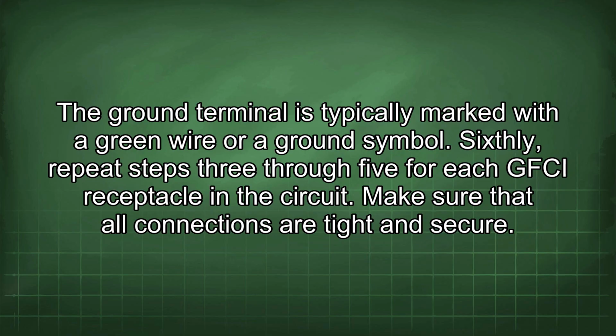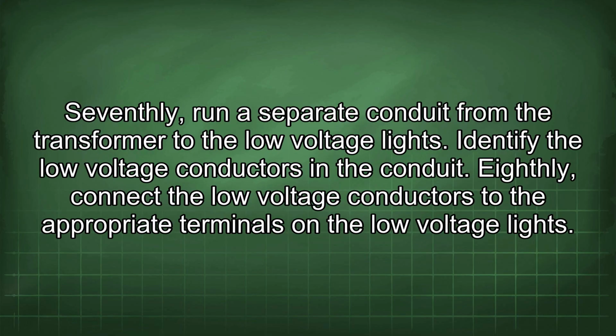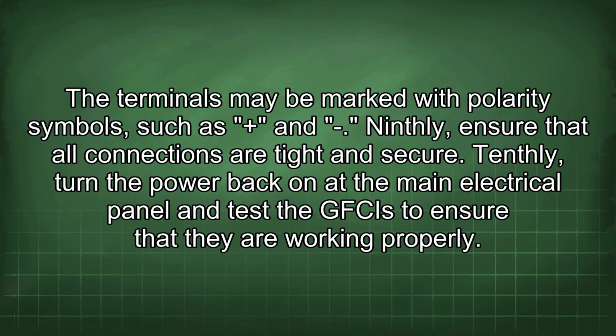Sixthly, repeat steps 3 through 5 for each GFCI receptacle in the circuit. Make sure that all connections are tight and secure. Seventhly, run a separate conduit from the transformer to the low voltage lights. Identify the low voltage conductors in the conduit. Eighthly, connect the low voltage conductors to the appropriate terminals in the low voltage lights. The terminals may be marked with polarity symbols such as plus and minus.